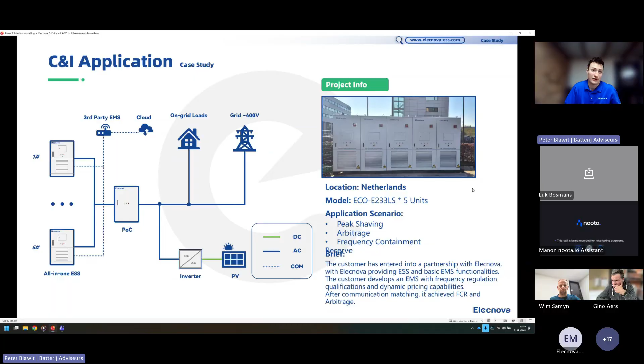But in essence, we have some solutions with an STS, that's the cabinet you see in the left picture, and on the right the battery cabinets. When the grid fails, it switches within 20 milliseconds to backup mode, so the batteries can still support the building or charge from the PV side. So if the grid fails, you will not lose power to your load or to your building, which helps a lot.